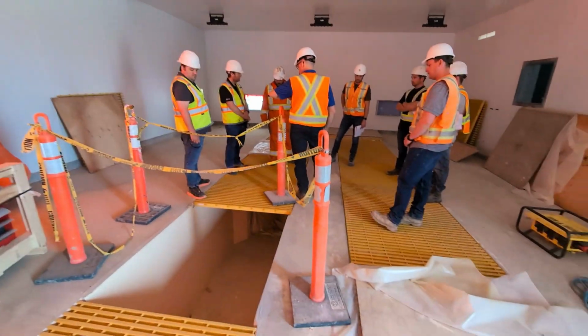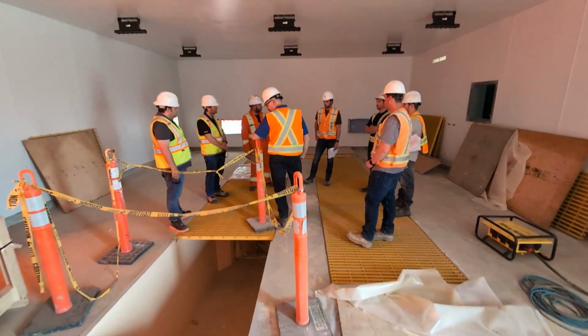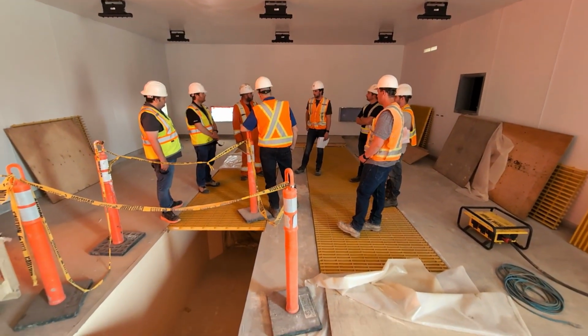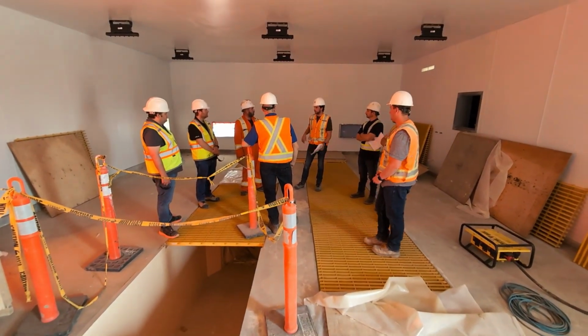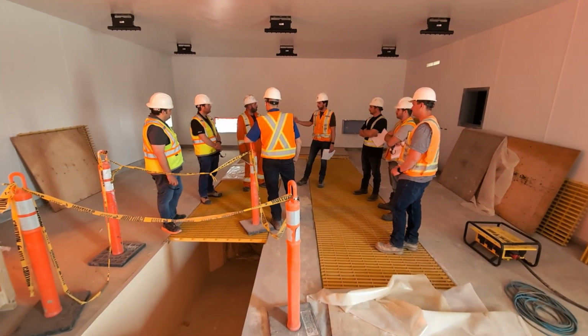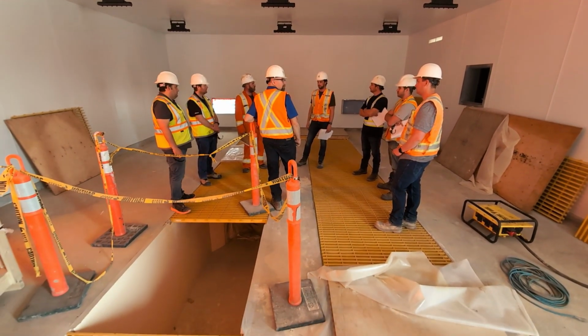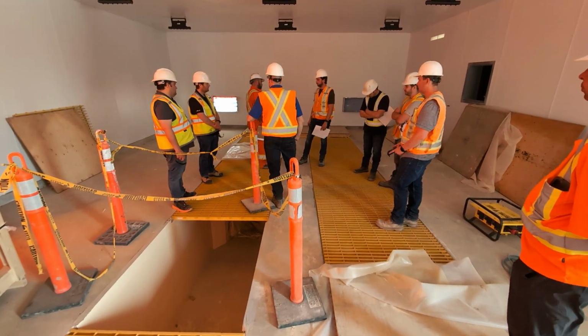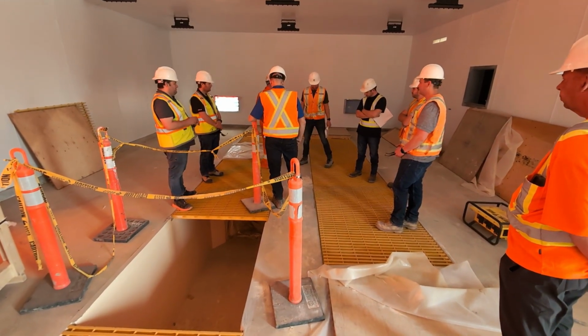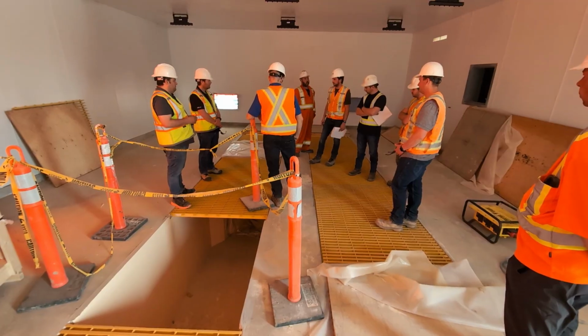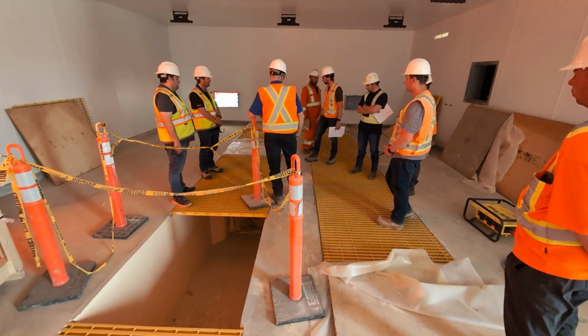It's just a direct math calculation. That's all the control system's doing, plugging the depth H into a math formula for this particular flume and spitting out a flow. So that's all the controls are doing. You can also do that manually, which is worth doing every now and then just to make sure things are accurate and the controls are doing what they do.